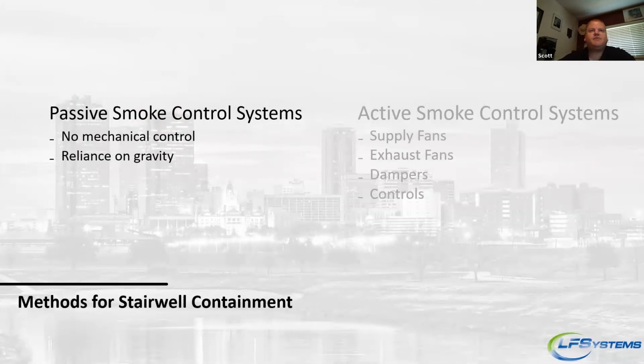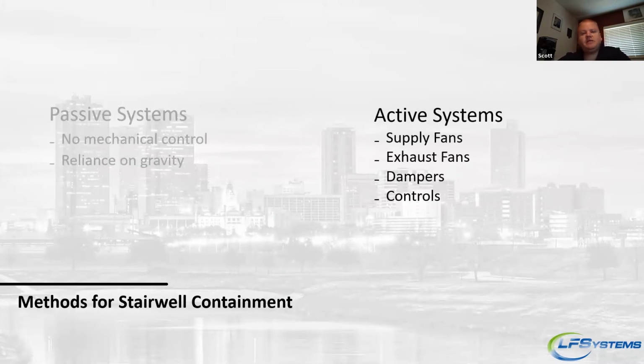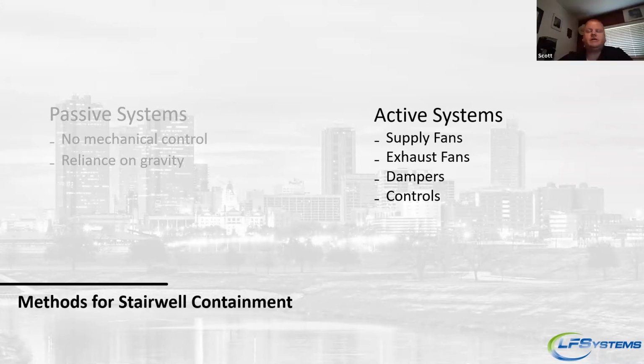Let's look at methods for stairwell containment. There are passive smoke control systems, which have no mechanical control. They pretty much rely on barriers and gravity. And then there are active systems, which have either supply fans or exhaust fans, dampers, and controls. Hey, Scott, I see a lot of examples of active smoke control systems in our environment. What would be a good example of passive smoke control systems in our work environment? Good question. Passive smoke control would be something like a heat smoke vent on the roof of an auditorium, or a gravity ventilator on a small stairwell, say a 2 to 3 story stairwell, something of that nature. Okay.